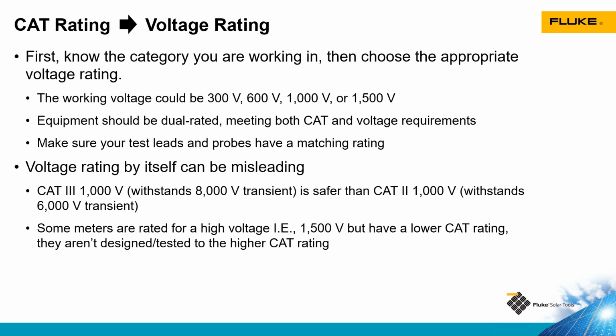So even though they're both 1,000 volt rated, because that category rating changed, the ability to withstand those transients is different. I also like to point out that some meters are able to test at a certain voltage, like 1,500 volts or even 2,000 volts. But when you dig into the specifications, you find that they're rated at a much lower level, like Category 3 1,000 volts or even Category 3 600 volts. They're not designed or tested at that higher testing rating, so they're going to be less likely to withstand a transient voltage spike than a tool that is properly rated.